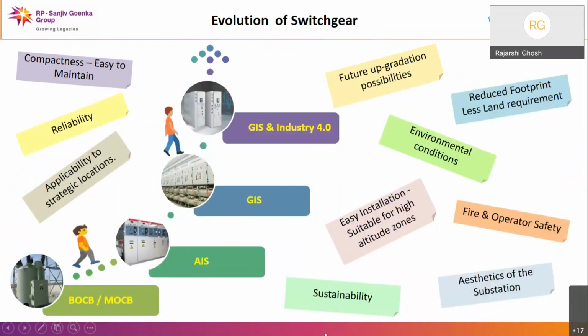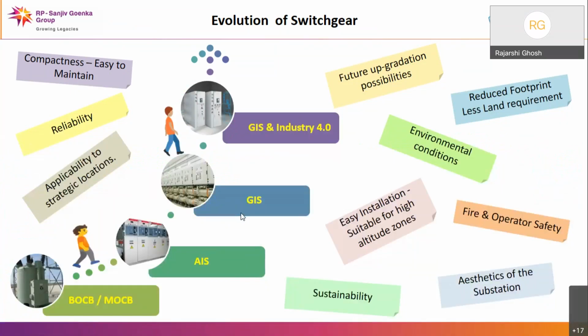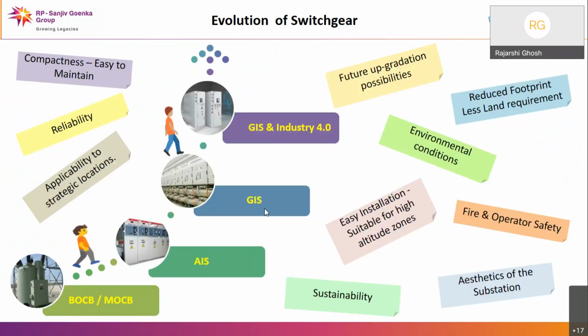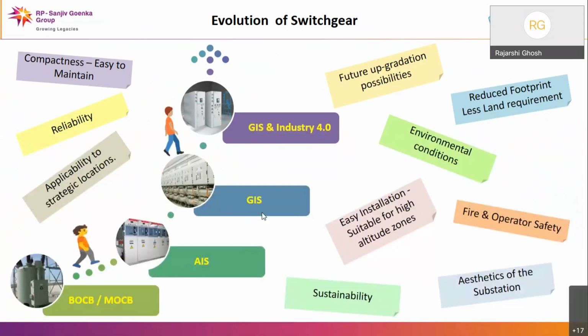Finally, the totally encapsulated gas insulated switchgear came. This gas insulated switchgear is entirely covered. There is no exposed part. So it requires very little maintenance, and it is much more reliable than all its earlier versions of AIS, MOCB, and previously the air circuit breakers. And now we are moving towards Industry 4.0. That means intelligent switchgear, which improves the reliability further.